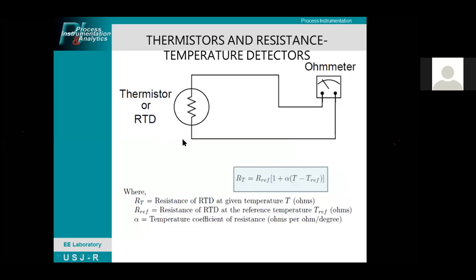So the temperature-resistance relationship is given by this formula: R sub T equals the reference resistance times the quantity 1 plus alpha times the temperature minus the reference temperature. Okay, so R sub T is the resistance of the RTD at a given temperature T, expressed in ohms. Then R reference is the reference resistance at the reference temperature, also in ohms. Alpha is the temperature coefficient of resistance, expressed in ohms per ohm per degree, or it could be ohms degree per ohm. So I have to verify this one for the unit. This is also a constant depending on the type of metal being used. Okay, so this is the temperature coefficient of resistance. Recall this formula.